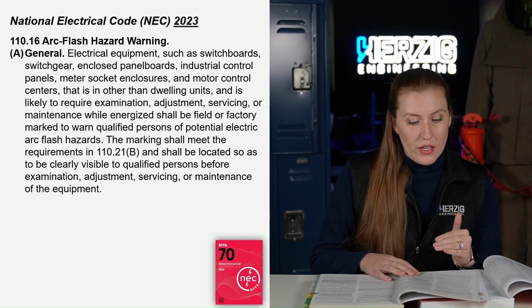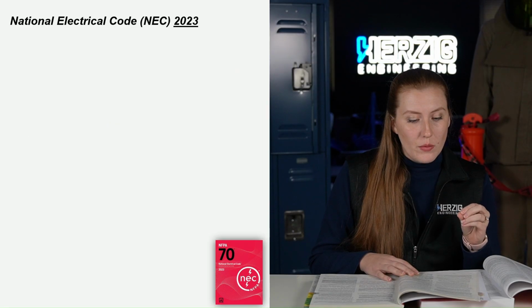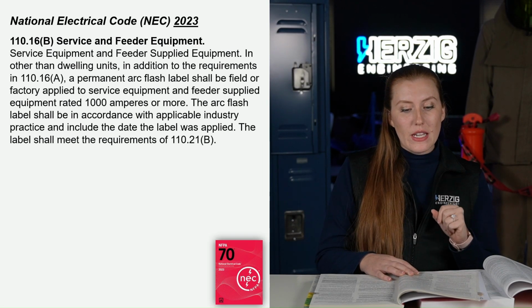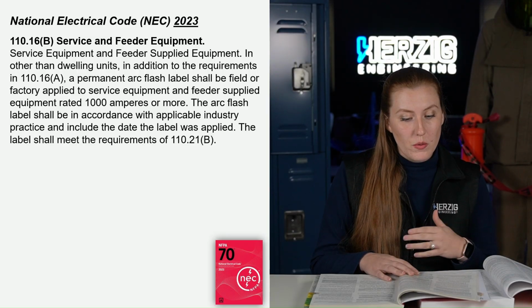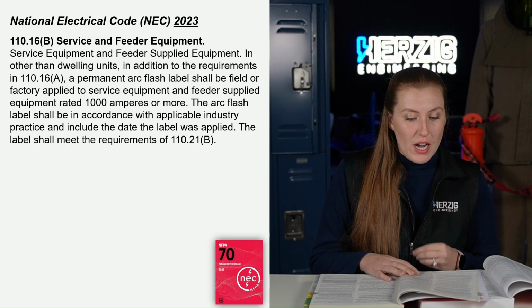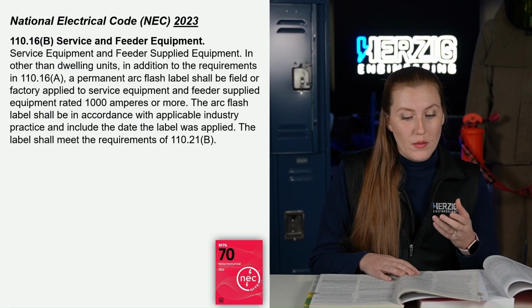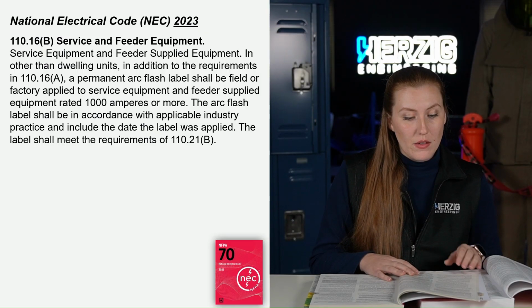In the 2023 edition, it specifies in that section that it'll be service and feeder supplied equipment rated 1,000 amps or more, and that the arc flash label shall be in accordance with applicable industry practices, including the date the label was applied. So the label shall meet the requirements of 110.21(B). Now, in the NEC 2023 edition, it still had the informational note below that telling you what the industry best practice standard was, the NFPA 70E, and then told you to go look at that for more details. So notice that it specifically said service equipment and feeder supplied equipment rated 1,000 amps or more.